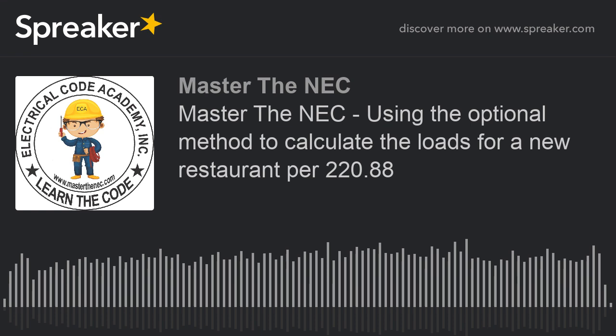Now let's talk about overload protection. Now, service conductors that come into a service enclosure do not have short circuit and ground fault protection. Okay, but they do have overload protection. And that's in accordance with 230.90 and meeting rules at 240.4. And so we have to make sure that we're protecting those service conductors from an overload condition.